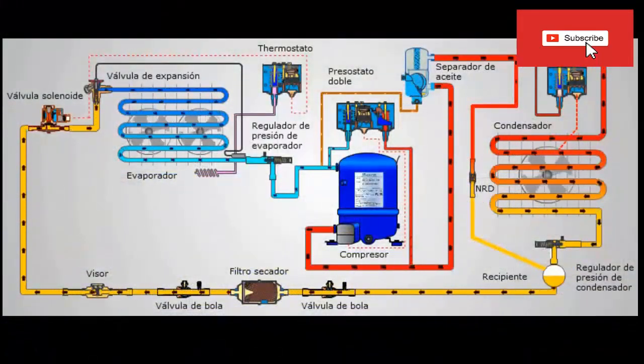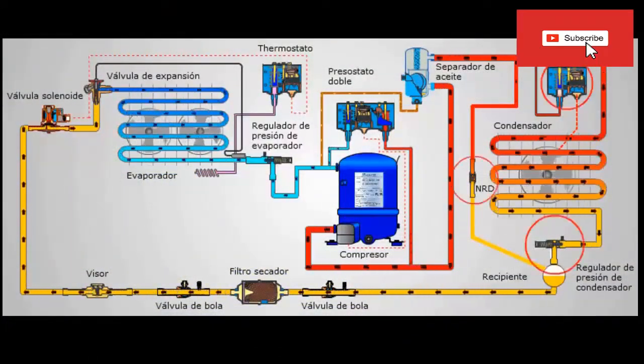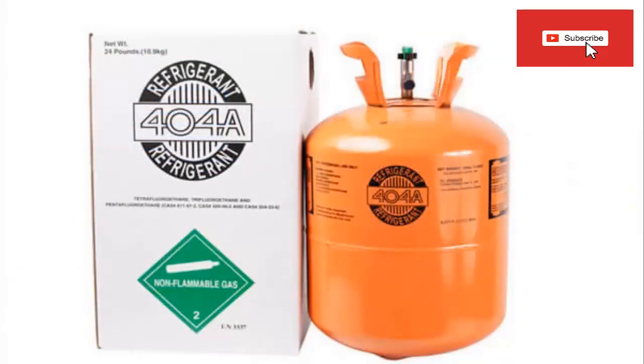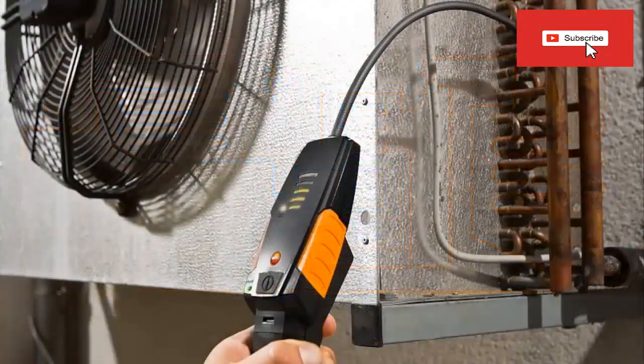The system that we are showing on the screen represents a commercial refrigeration circuit that until a few days ago was working with R404A refrigerant gas. This system was used to generate an evaporator temperature of -20 degrees Celsius. Product of an anomaly, a massive refrigerant leak originated, therefore it is required to recharge the installation with gas again.